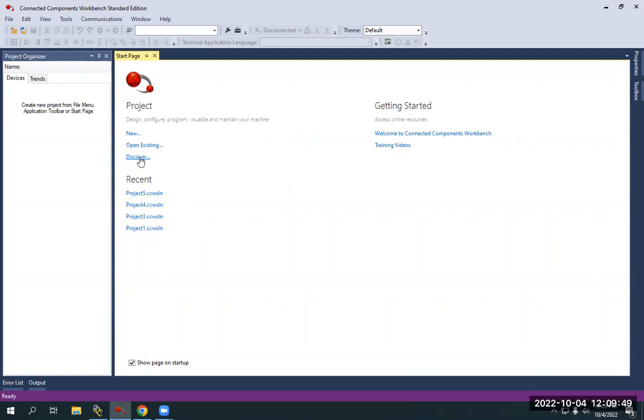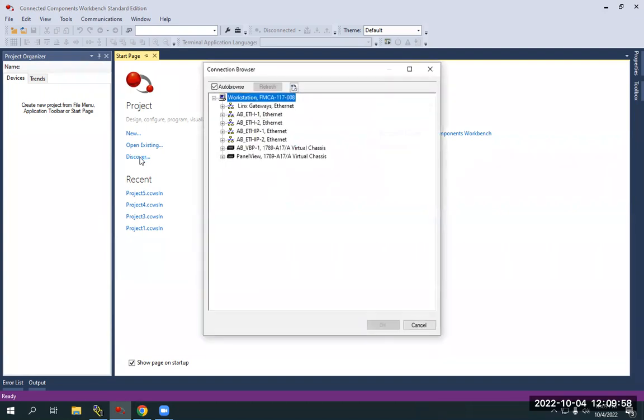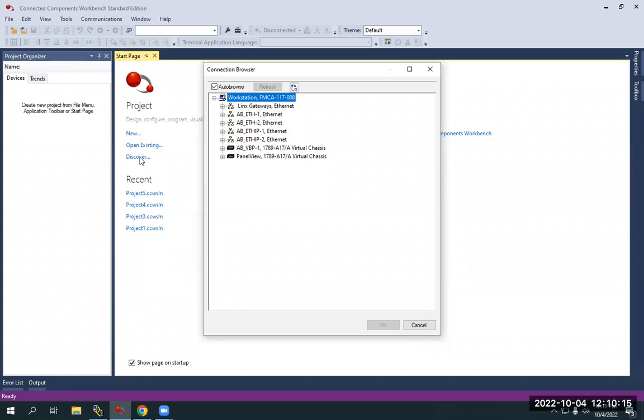So what I'm going to do is I'm actually going to do the Discover. So I'm going to look for the PLC and then I'm going to upload the program from the PLC to the computer. And remember that in programmable logic controllers, you are uploading from the PLC to the computer and you are downloading from the computer to the PLC. So it sounds opposite of what you think it would actually be. But if you're uploading, you're actually pulling up the file or the program from the PLC itself so you can view it on the computer. If you build a program on the computer and then you want to send it to the PLC, you would actually download it to the PLC. But again, we'll get that terminology and everything straightened out once we go through a few more classes.